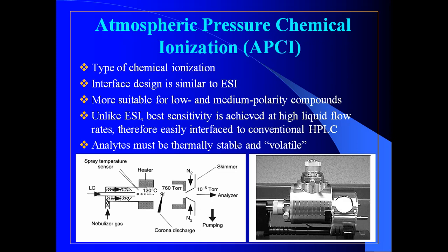The liquid is introduced through a zero volume LC fitting on the probe handle, from where it flows through the stainless steel tubing. The high velocity jet of nebulizer gas flows coaxially over the sprayer and disperses the sample as a mist of fine particles.